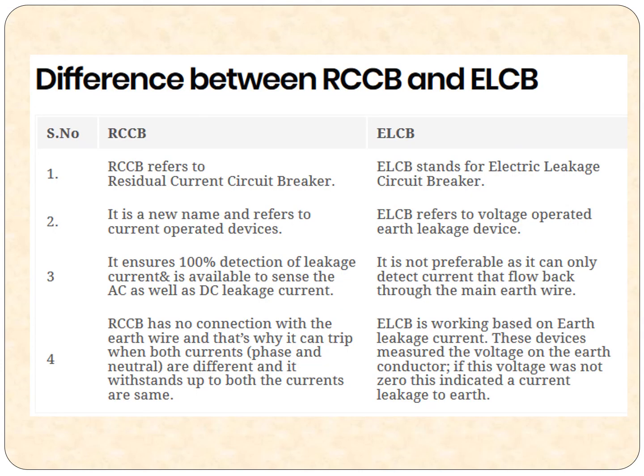So let us consolidate the difference. RCCB is the new name and refers to the current operated device, and ELCB is the voltage operated earth leakage device. RCCB ensures 100% detection of leakage current and can sense AC as well as DC leakage currents. ELCB is not preferable as it can only detect current that flows back through the main earth wire. That is, if your earth wire has a current flow, then it will sense. RCCB has no connection with the earth wire, and that's why it can trip when the phase and neutral currents differ, and it withstands while both currents are the same, which means if an abnormality happens, your phase current will not be equal to your neutral current.